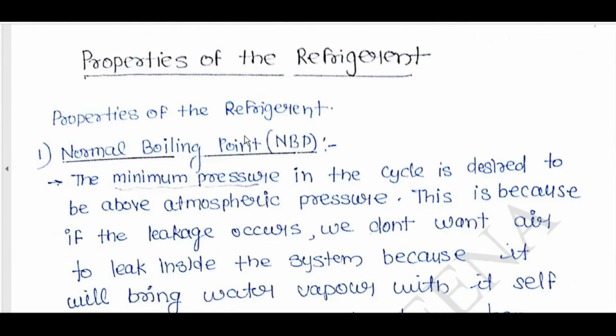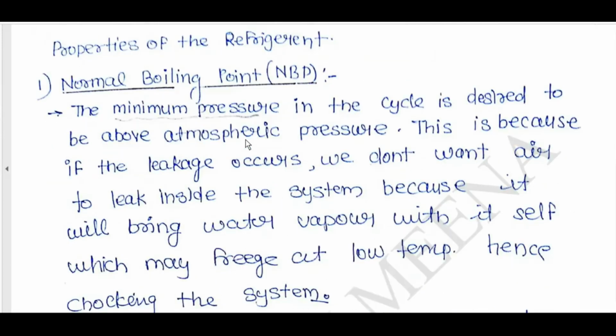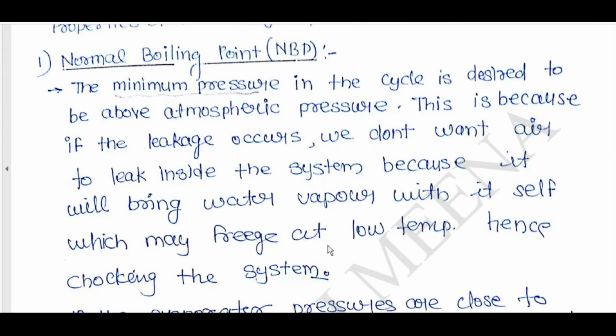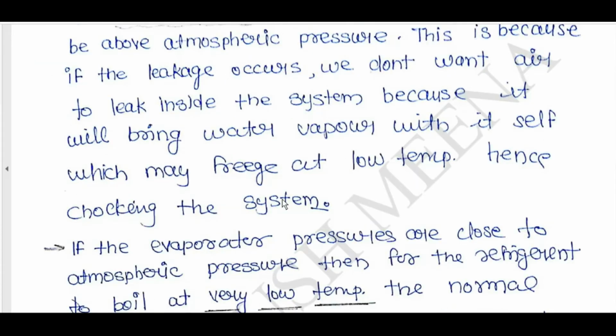Properties of refrigerant: normal boiling point. The minimum pressure in the cycle is desired to be above atmospheric pressure. This is because if leakage occurs, we don't want air to leak inside the system, because it will bring water vapor with it, which may freeze out at low temperature, hence choking the system.